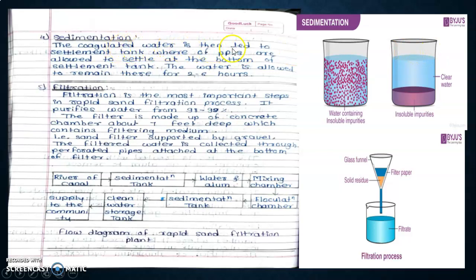Sedimentation: the coagulated water is then led into settlement tank where precipitations are allowed to settle at the bottom of the settled tank. The water is allowed to remain there for 2 to 6 hours.